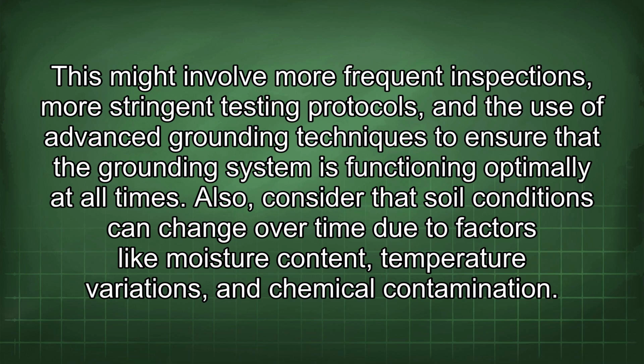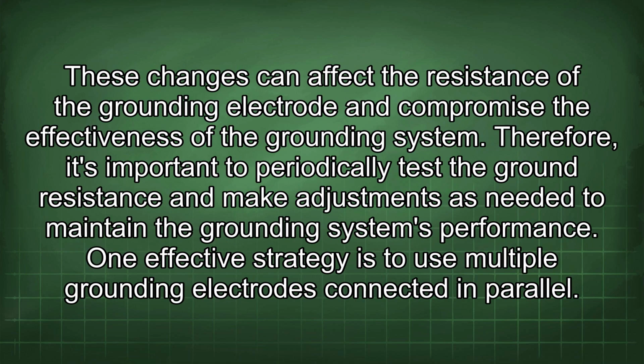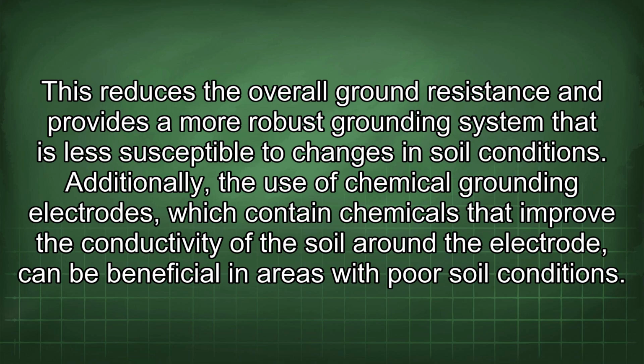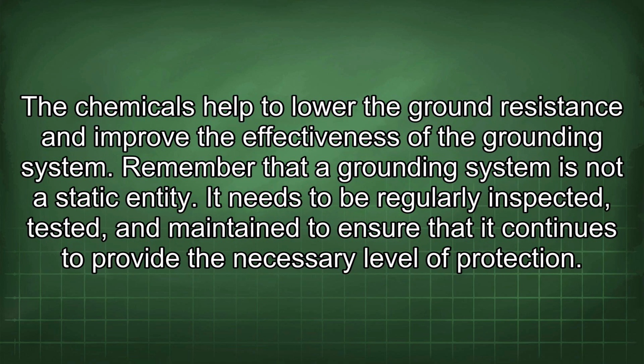Also, consider that soil conditions can change over time due to factors like moisture content, temperature variations, and chemical contamination. These changes can affect the resistance of the grounding electrode and compromise the effectiveness of the grounding system. Therefore, it's important to periodically test the ground resistance and make adjustments as needed to maintain the grounding system's performance. One effective strategy is to use multiple grounding electrodes connected in parallel. This reduces the overall ground resistance and provides a more robust grounding system that is less susceptible to changes in soil conditions. Additionally, the use of chemical grounding electrodes, which contain chemicals that improve the conductivity of the soil around the electrode, can be beneficial in areas with poor soil conditions.